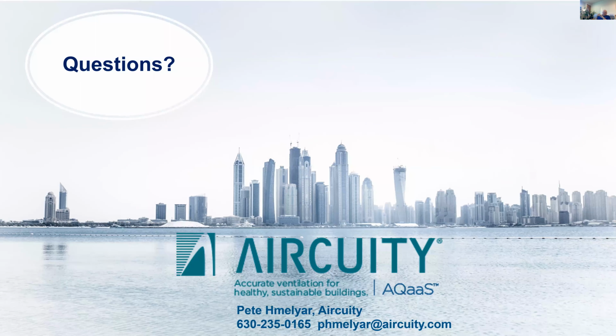Thank you. We've got another question as well that came through earlier. Are there other types of research buildings that can use the Aircuity system? Yes, the main other research building that we're involved with now, finally in Canada, because some new guidelines for CCAC changed, are the vivariums. Vivariums are the animal holding areas where the animals that are used in research are held. We have been doing this in the States and other parts of the world for many years, but just in the last maybe 2 or 3 years, the CCAC changed their standards and allowed Canadian vivariums to vary the air change rate like we do in labs.